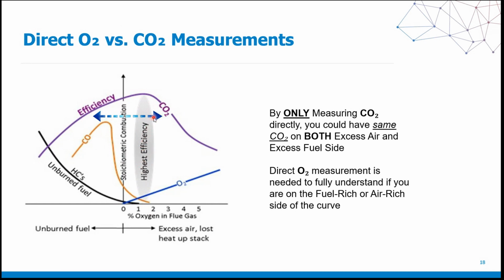Because if we negate oxygen, we are negating what proper combustion is, because it begins and ends with oxygen. It's one of the most important, if not the most important factor when we discuss combustion. But if we look over here, the CO2 up here is fine. Our oxygen level is right in this shaded area here. Our CO is right in that 0 to very negligible amount right here that we see.